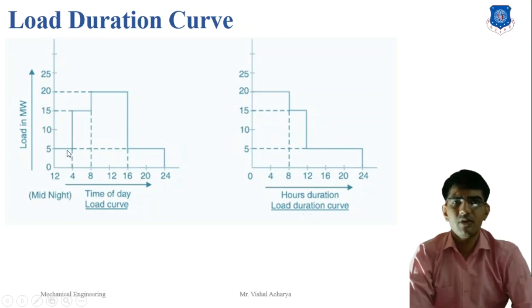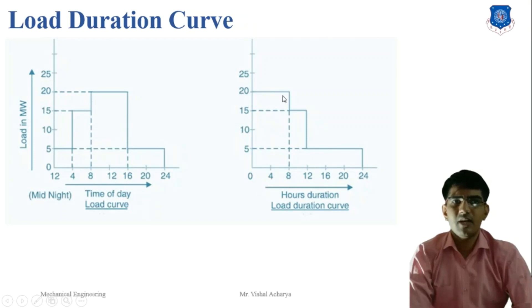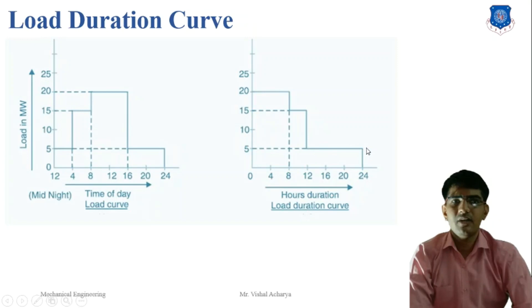Here is an example representing the load curve: from 12 to 4 hours, 5 MW load is required; from 4 to 8 hours, 15 MW load is required; from 8 to 16 hours, 20 MW load is required; from 16 to 24 hours, 5 MW load is required. For the load duration curve, we first find the maximum load, which is 20 MW for 8 hours. So we plot 0 to 8 hours at 20 MW; then 15 MW for a 4-hour duration from 8 to 12; then 5 MW for the remaining 12 hours — 4 hours from 12 to 4 plus 8 hours from 16 to 24. This is the process for plotting the load duration curve.